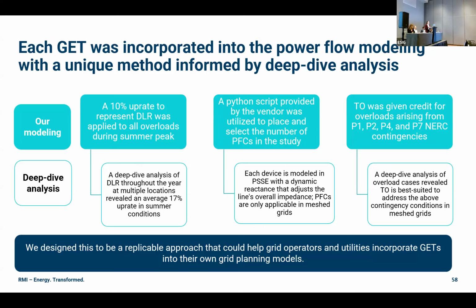With power flow controllers, it was a little different. We were able to model power flow controllers in PSSE with a dynamic reactance to adjust the line's impedance. And that was able to optimize and select the number of and placement of power flow controllers in the study. Finally, we worked with NewGrid to conduct a deep dive analysis of some overload cases to figure out where topology optimization is best suited to address certain contingency conditions, like the NERC P0 through P7 contingency conditions. And we gave topology optimization credit for P1, P2, P4, and P7 conditions.